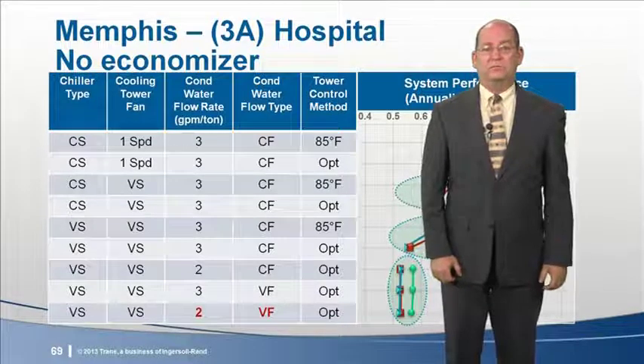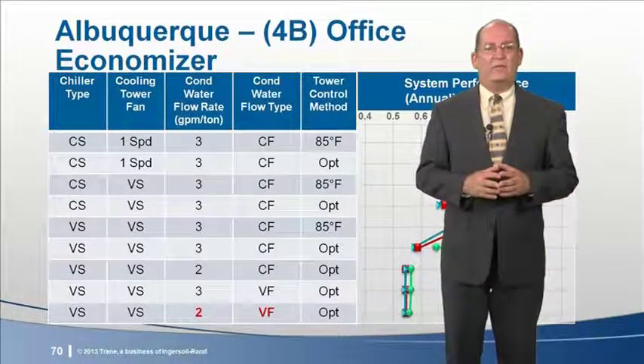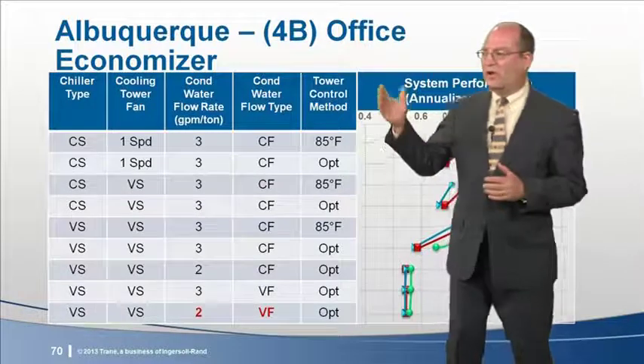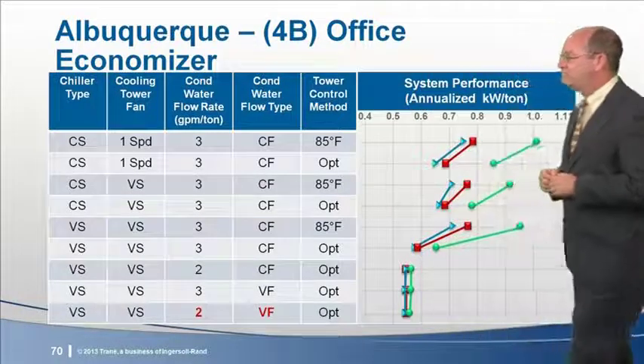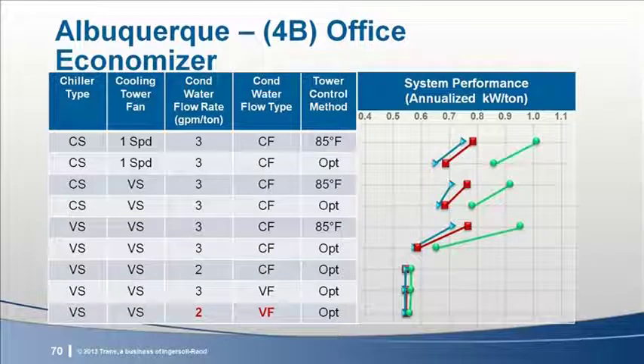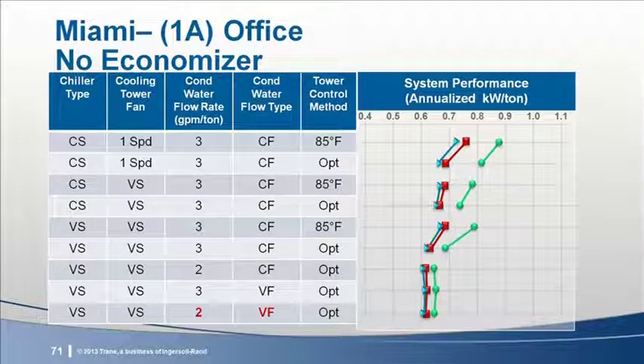So let's try a dry climate with an economizer. Here's an office building in Albuquerque. Again, the trends look very similar. We started asking ourselves if there is any climate where there is a difference. Let's look at an office without an economizer in Miami. The only thing we see different is that in this climate, reduced design condenser water flow rate, 2 GPM per ton, gives more savings.